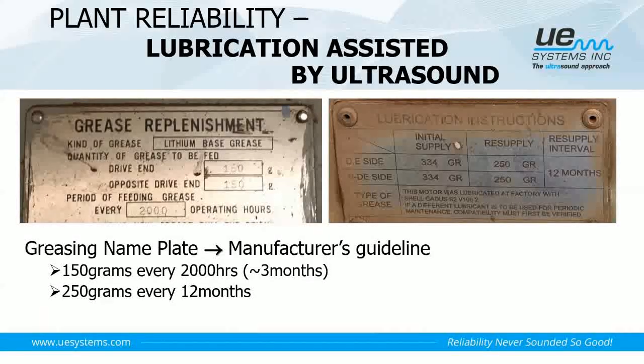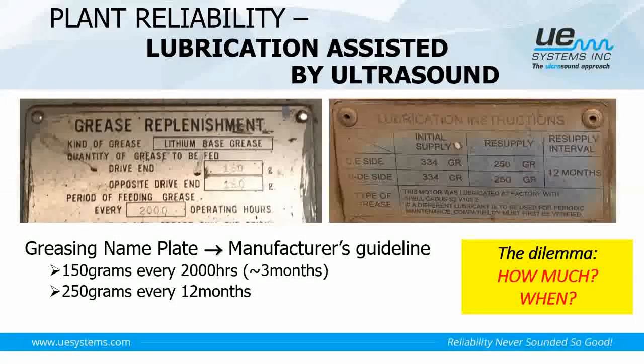We grease according to the recommendation from the manufacturer, based on the grease plate. This is just the manufacturer's guideline or recommendation to the end user. The manufacturer has no control over the loading, how much you run the motor, whether at 100%, 20%, or 50%. They have no control over where you locate your motor, outdoor or indoor, in hot temperature or underground. So this will also affect the grease consumption within the bearings.